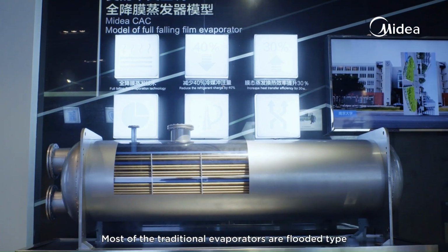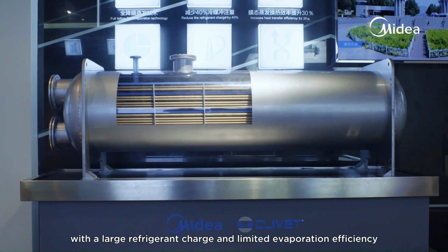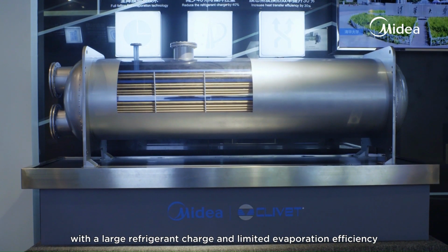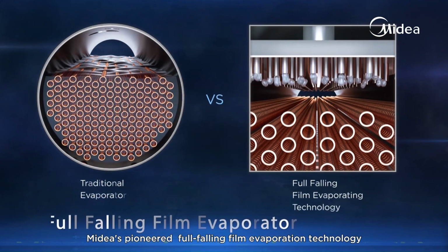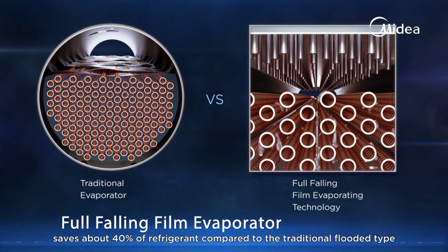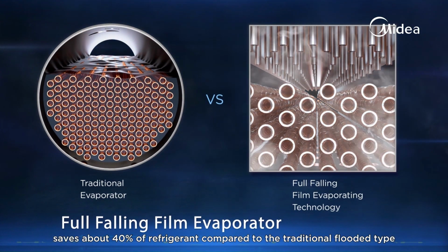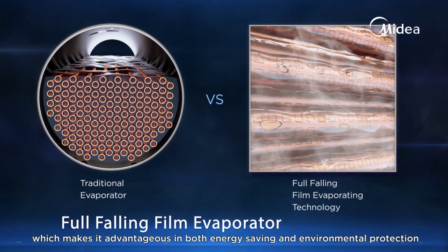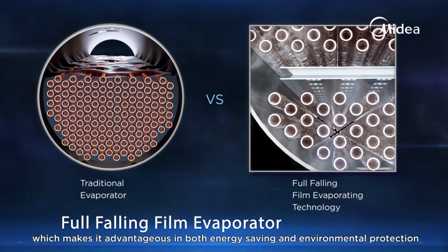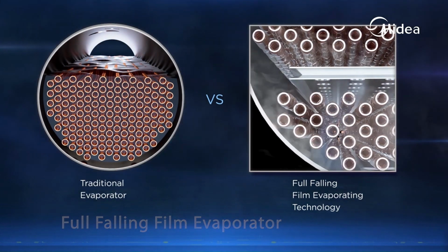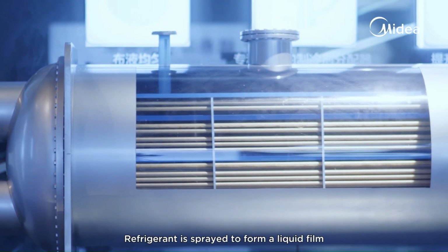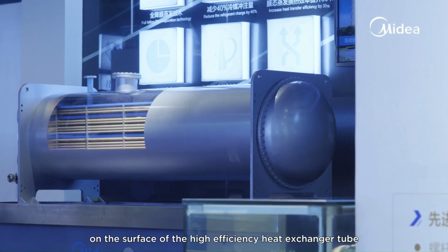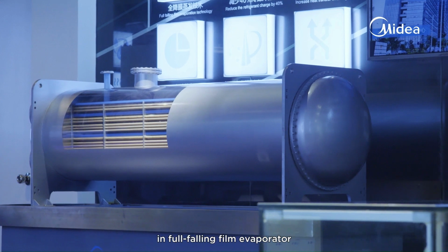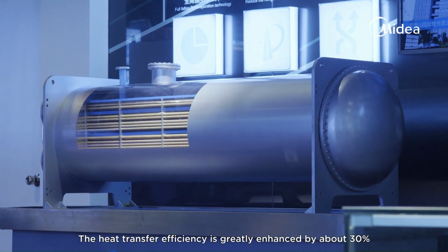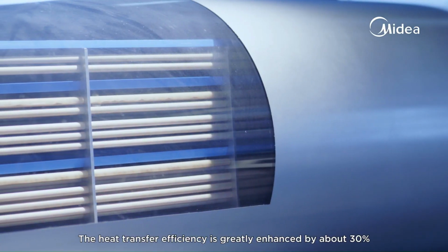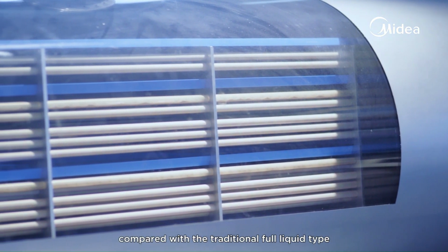Most of the traditional evaporators are flooded type, with a large refrigerant charge and limited evaporation efficiency. MIDEA's pioneered full-falling film evaporation technology saves about 40% of the refrigerant compared to the traditional flooded type, which makes it advantageous in both energy saving and environmental protection. Refrigerant is sprayed to form a liquid film on the surface of the high-efficiency heat exchanger tube in full-falling film evaporator. The heat transfer efficiency is greatly enhanced by about 30% compared with the traditional full liquid type.